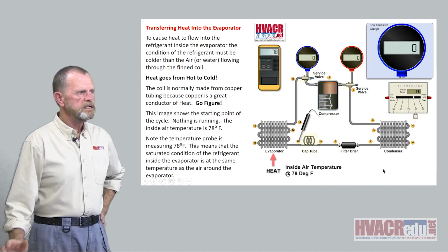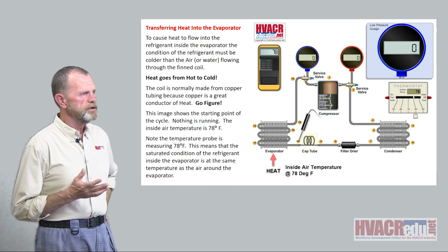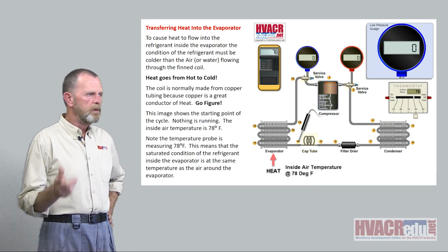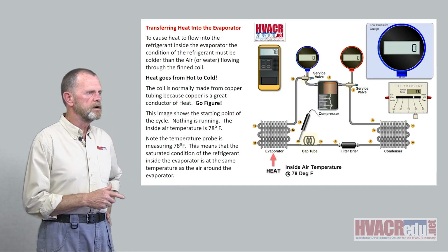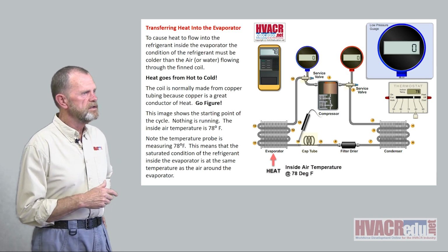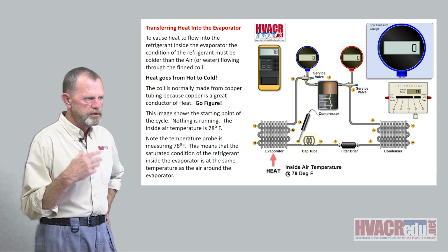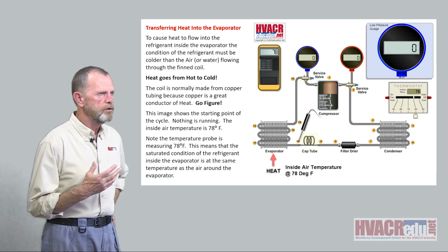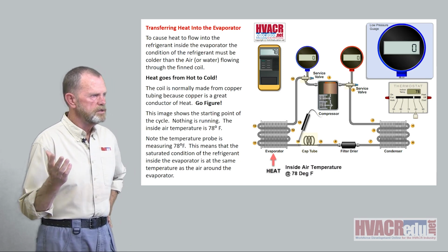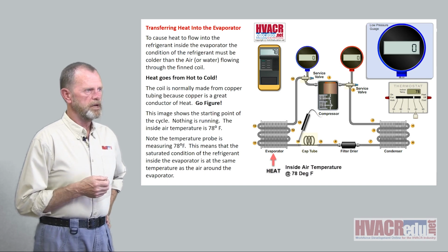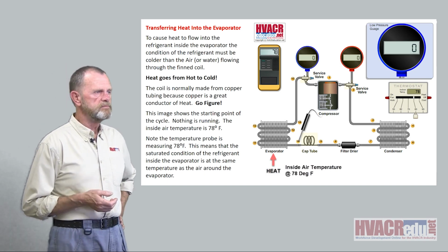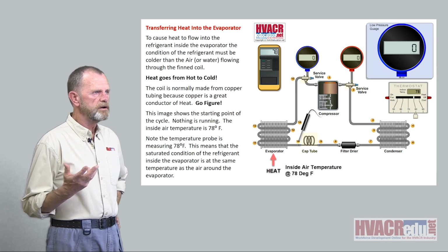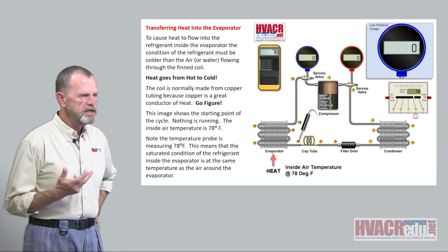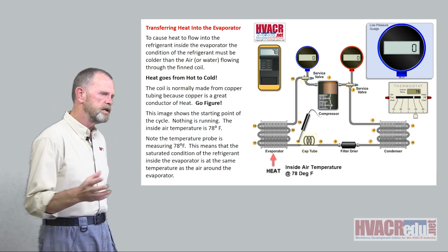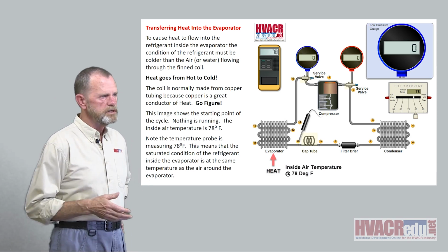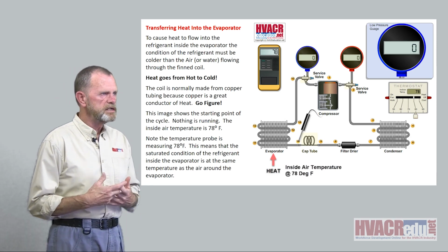So, to cause heat to flow into the refrigerant inside the evaporator, the refrigerant must be colder than the air or water flowing through the fins and past the coil, whether it's the water chiller barrel or an air coil. Heat goes from hot to cold. Once again, the coil is normally made of copper tubing because copper is a great conductor of heat. Go figure, right? So, when you're trying to move heat and get it away from somewhere, you don't want to slow it down, so you use materials that conduct heat the best.